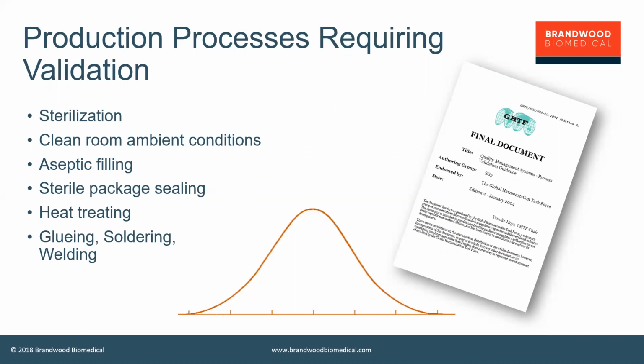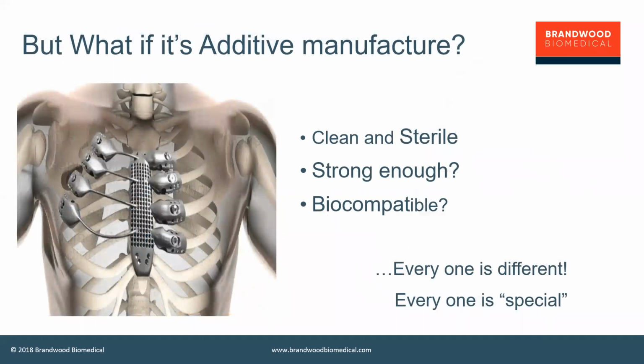But really, when you have custom devices, you have to bring the same principles into the design phase. So you need to be thinking about, okay, how can we apply generic principles to a product design where we can't actually test the product without breaking it? So if the device is an additive manufactured device, the examples we gave at the beginning that we're going to focus on in this webinar, it needs to be clean and sterile, it needs to be strong enough, and it needs to be biocompatible. But every one of these devices is different, and so every one is essentially special in terms of a special process in its manufacture.